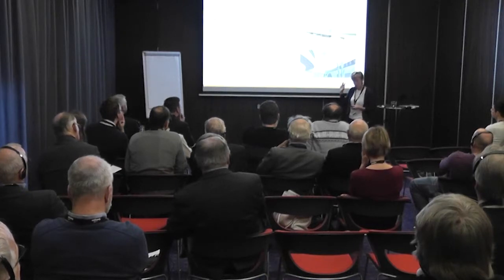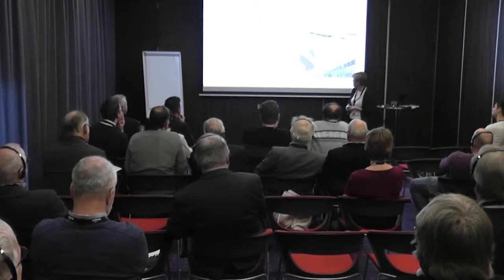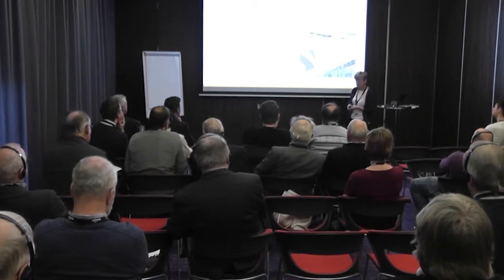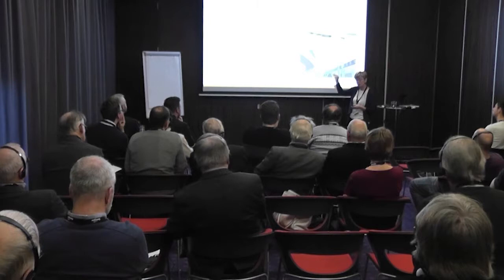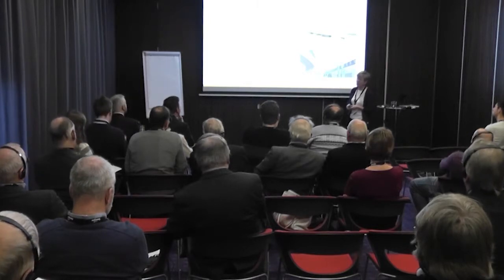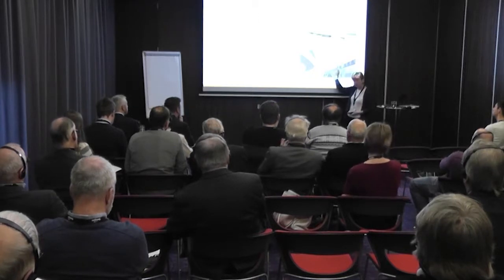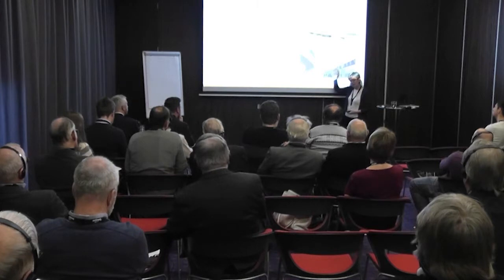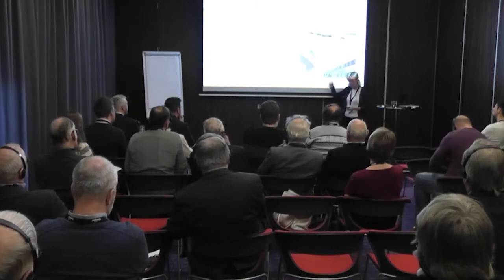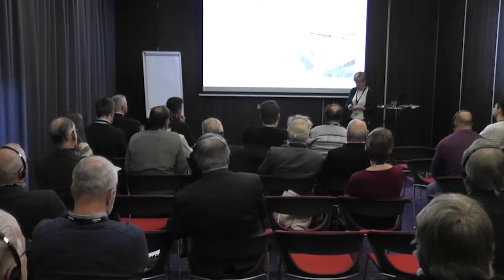But still, people are very satisfied and happy with the situation, even though there's not any heavy heaters in this room. So this means that these shelves work and stop the draft from the window. And one other good thing is that we avoid having warm air passing the window and increasing the heat loss. So it's also a very good energy efficiency in having this solution.